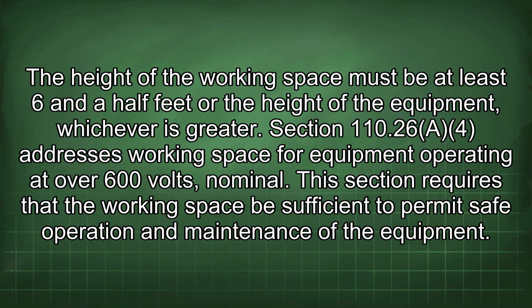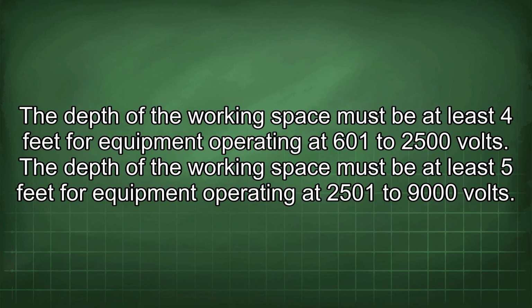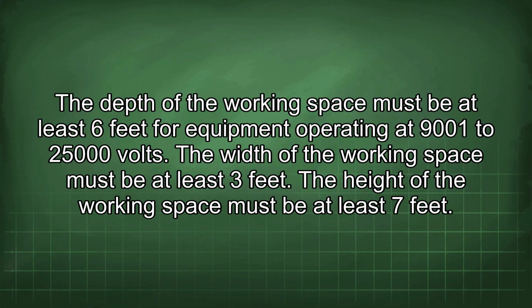Section 110.26 addresses working space for equipment operating at over 600 volts, nominal. This section requires that the working space be sufficient to permit safe operation and maintenance of the equipment. The depth of the working space must be at least 4 feet for equipment operating at 601 to 2500 volts. The depth must be at least 5 feet for equipment operating at 2501 to 9000 volts. The depth must be at least 6 feet for equipment operating at 9001 to 25000 volts.